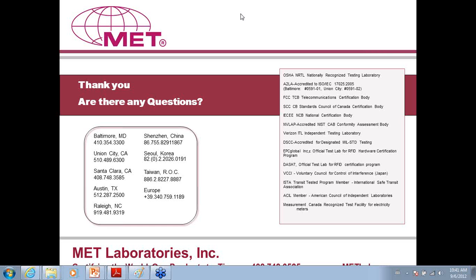The second question, and I'll read it: which portion of the testing have we seen the most failures? We have seen failures across the board. We have seen failures with the noise testing. However, a large percentage of the failures we are seeing are with the overvoltage transients, because the majority of the board components are designed for telecommunication systems. Generally speaking, and I'm being very general, they are designed so that their protection will operate around, say, 85 volts. Whenever there is a voltage on the DC bus that goes beyond 85 volts, they shut down to protect themselves, and the system will indicate a failure.